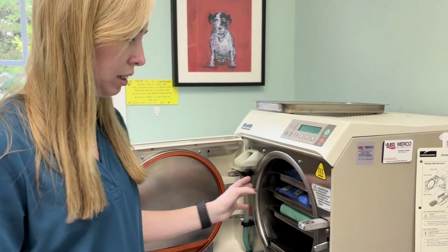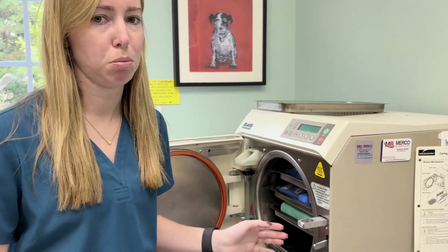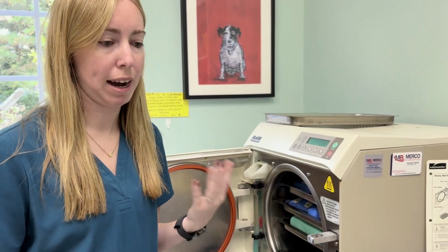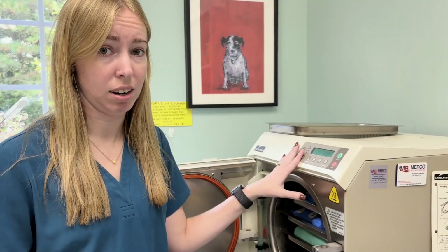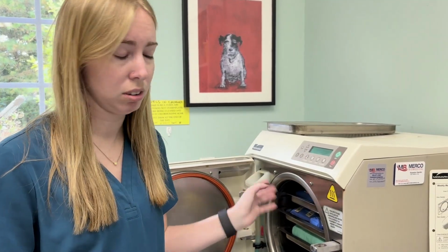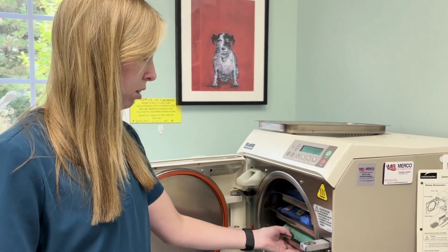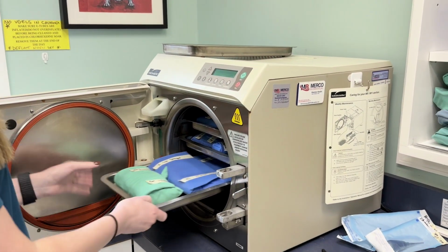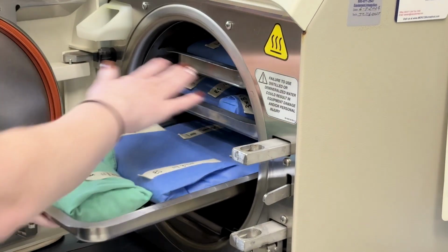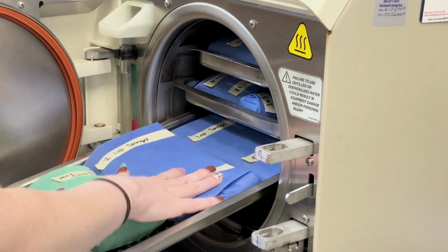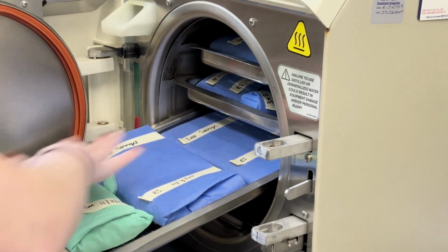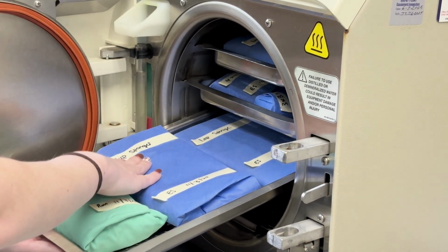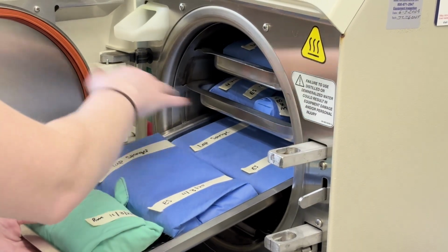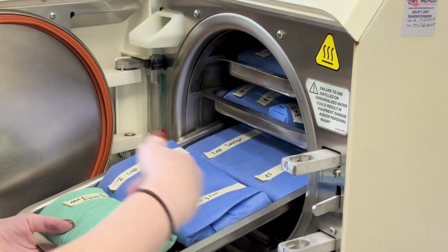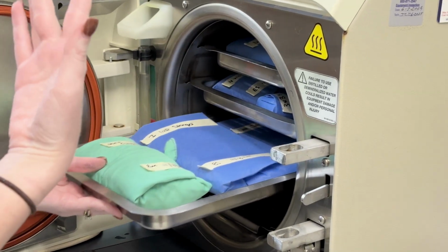How to load one: this is used for any surgical instruments, surgical packs. If we put them in packs versus pouches, we turn it on to different settings. Gowns too. Anything like that we would sterilize for the surgical room and procedures. I've already loaded the autoclave. There are multiple shelves in here, and you want to add your packs in one row. You don't want to stack them on top of each other, or they won't sterilize properly. These all have some room in between the packs as well for the steam to go through.